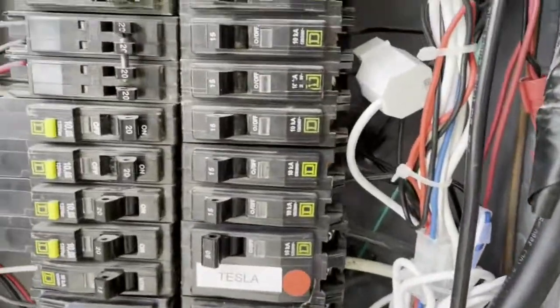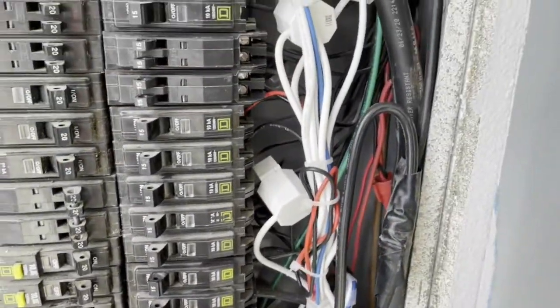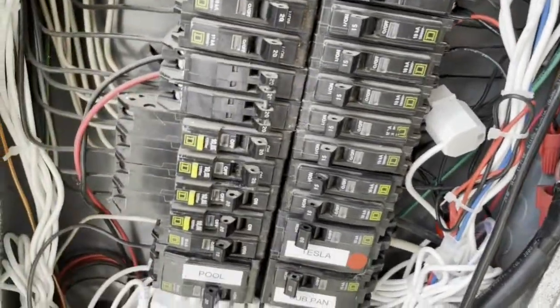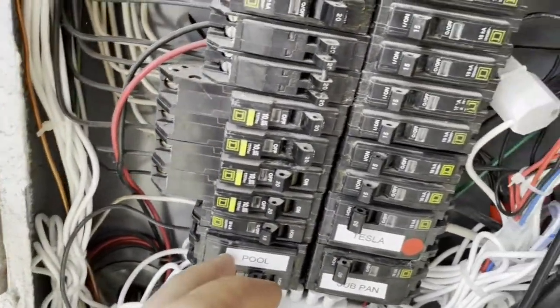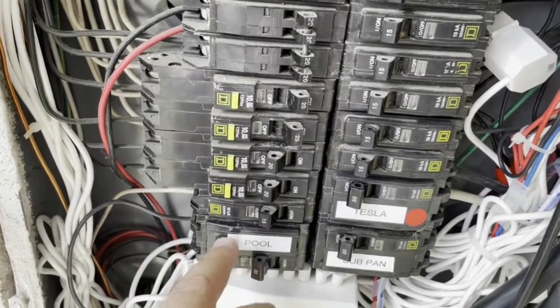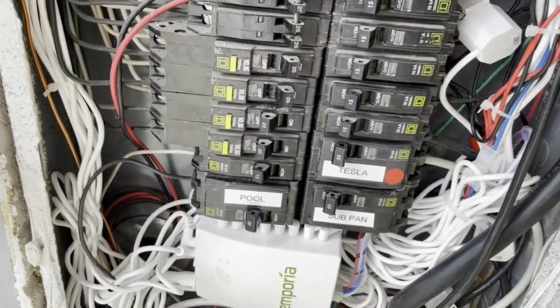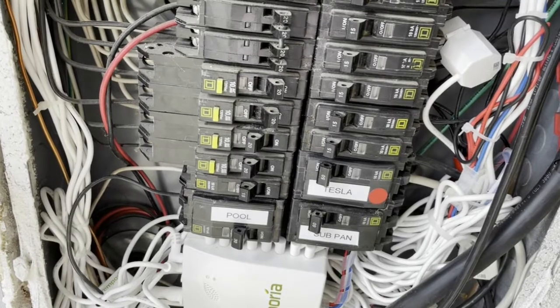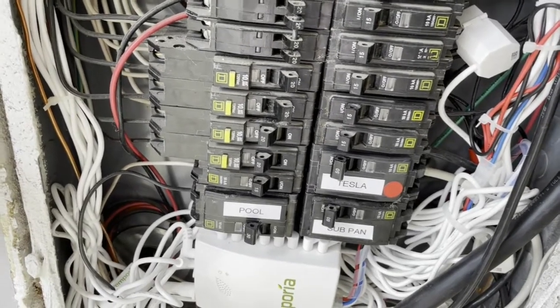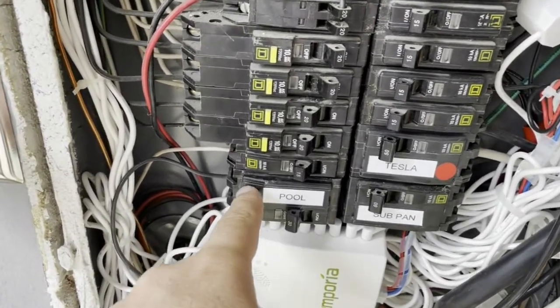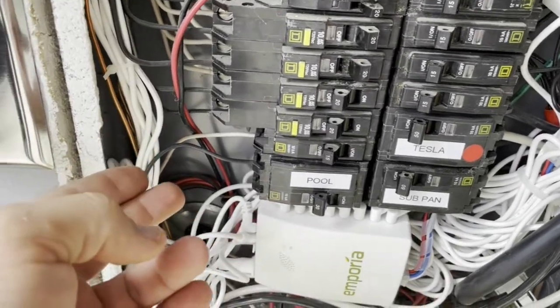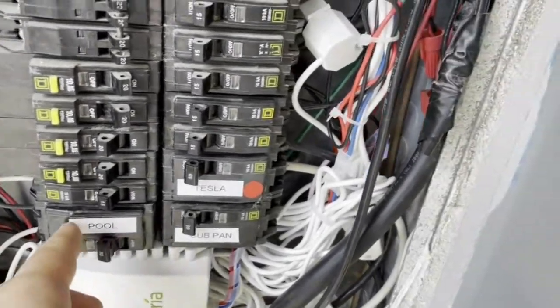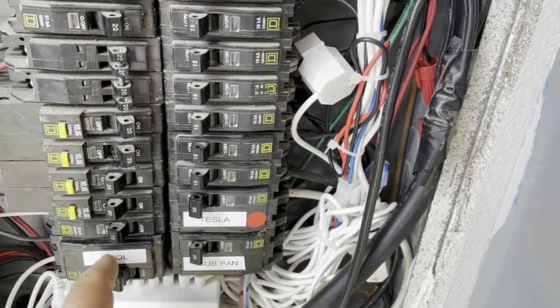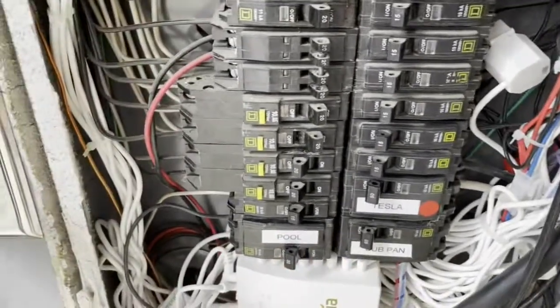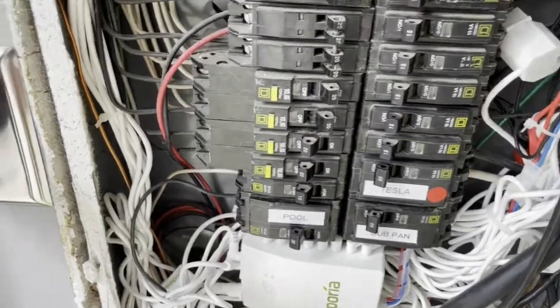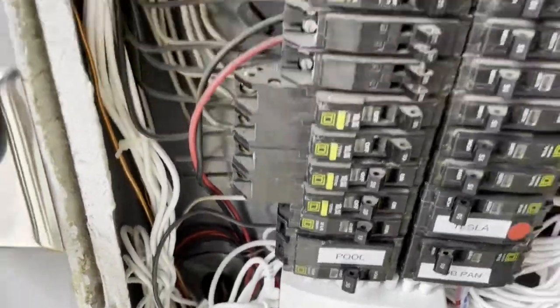For the EV charger and other equipment like the pool, if they're all 240, that means you have balanced loads. But if something on your pool panel is 110, it's getting power from one side or the other, so you may want to put 2 sensors. In my case, the cleaner booster pump, the pump, and the water heater are all connected to 240, so it's a balanced load and I just need one sensor.